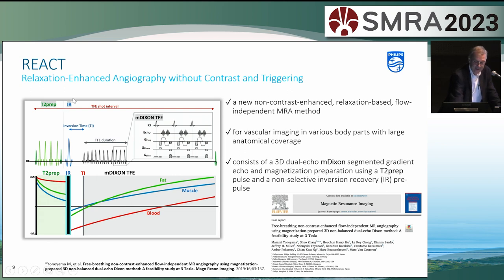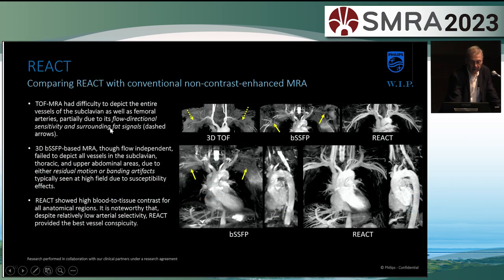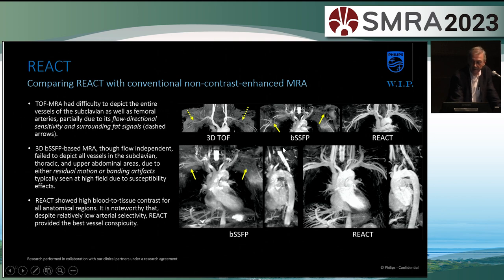REACT stands for Relaxation Enhanced Angiography without Contrast and Triggering. So it's not only without contrast, it's also without triggering — you don't need physiological synchronization, neither cardiac nor respiratory. It can be used for vascular imaging in various body parts. It consists of magnetization preparation using T2 prep and a non-selective IR pulse, and is also acquired with M-Dixon. If you look at a comparison of TOF, balanced steady-state free precession, and REACT: in TOF, reverse flow is not visualized well; with balanced sequences, especially at a larger field of view, you get banding artifacts. In REACT, it's pretty free of all these artifacts.